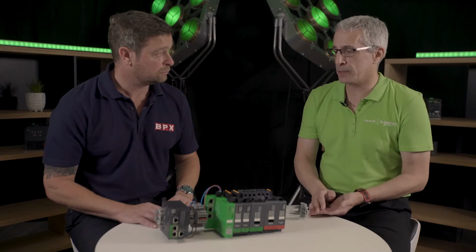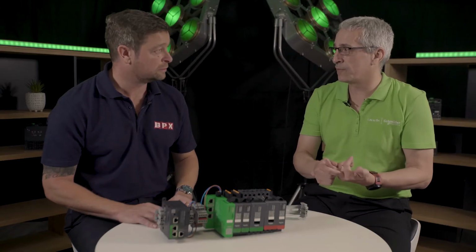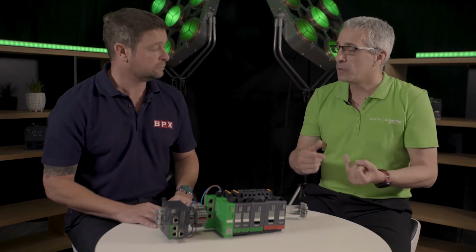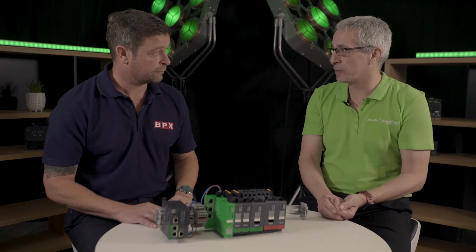Then there's the concept of digital twins. It's replicating the function that you're trying to design, and you can do that from the very early stages. So we've got a lot of online tools that allow you to select an avatar, select a pump avatar, select a star delta avatar. You then put in the details of what you're trying to do. So you've got the kilowatt rating of the motor. You've got a temperature sensor in there. You've got maybe a process variable of maybe water flow or sump level. You put those details into the online tool, and it comes out with a bill of materials for the product.